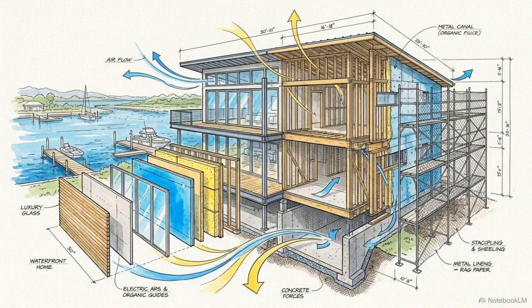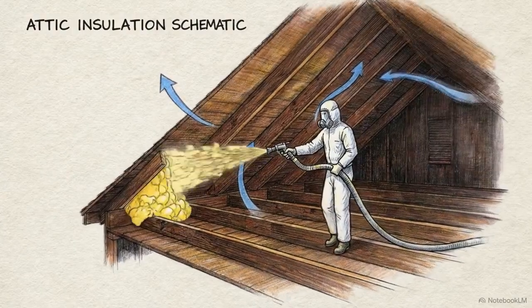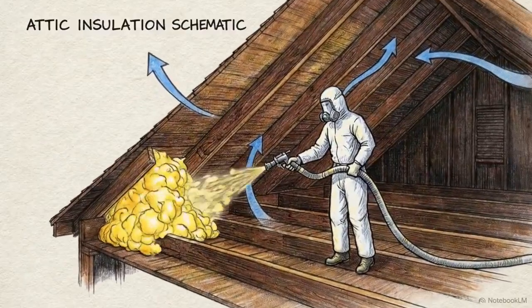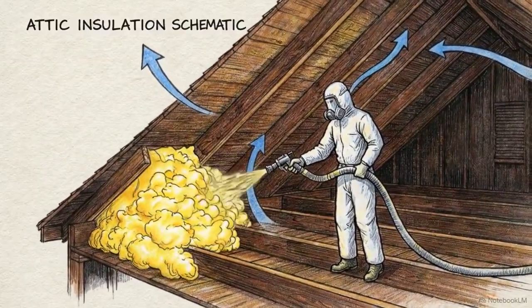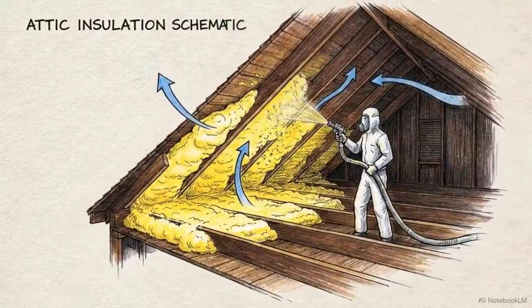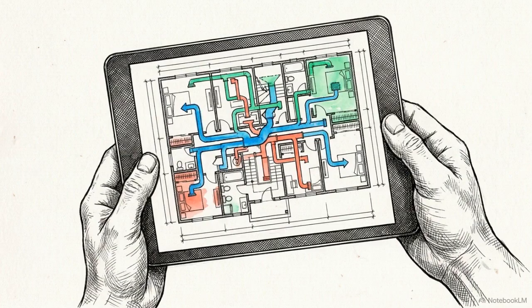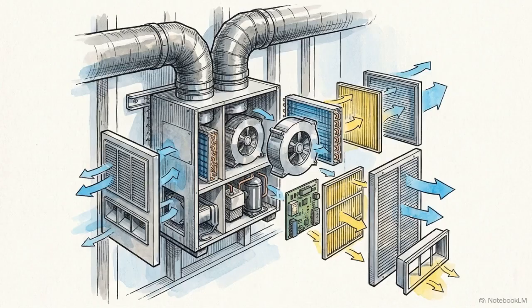In modern high-end coastal construction, the standard practice for controlling indoor air quality starts at the top. Builders seal the building envelope, typically applying spray foam insulation directly to the attic roof deck to block out humid exterior air. Next comes the mechanical load. HVAC systems are precisely sized using manual J load calculations, and a dedicated whole-home dehumidifier is installed to manage whatever moisture remains inside that sealed environment.